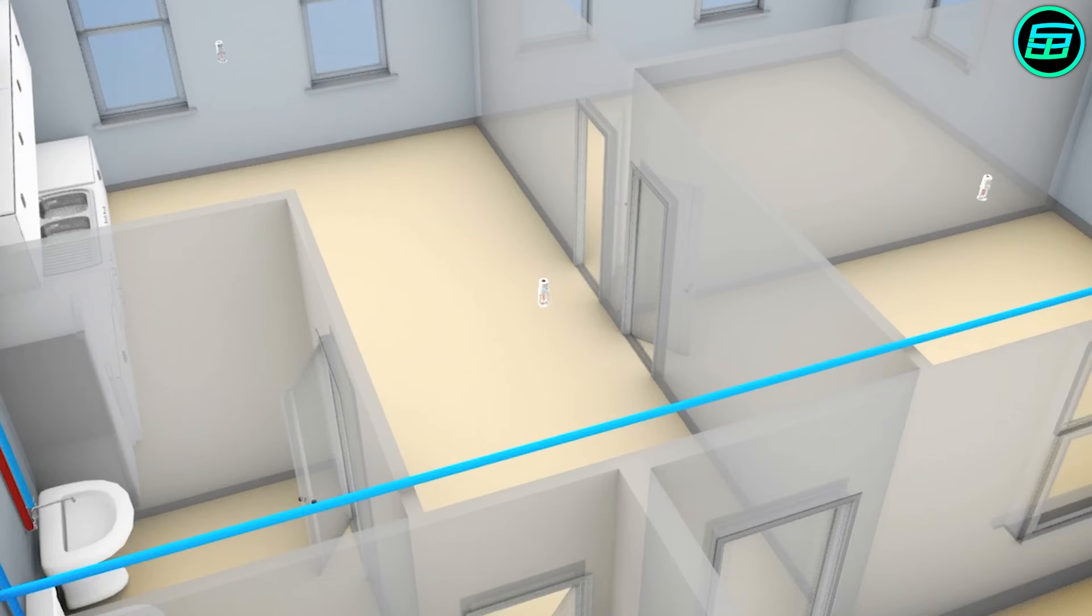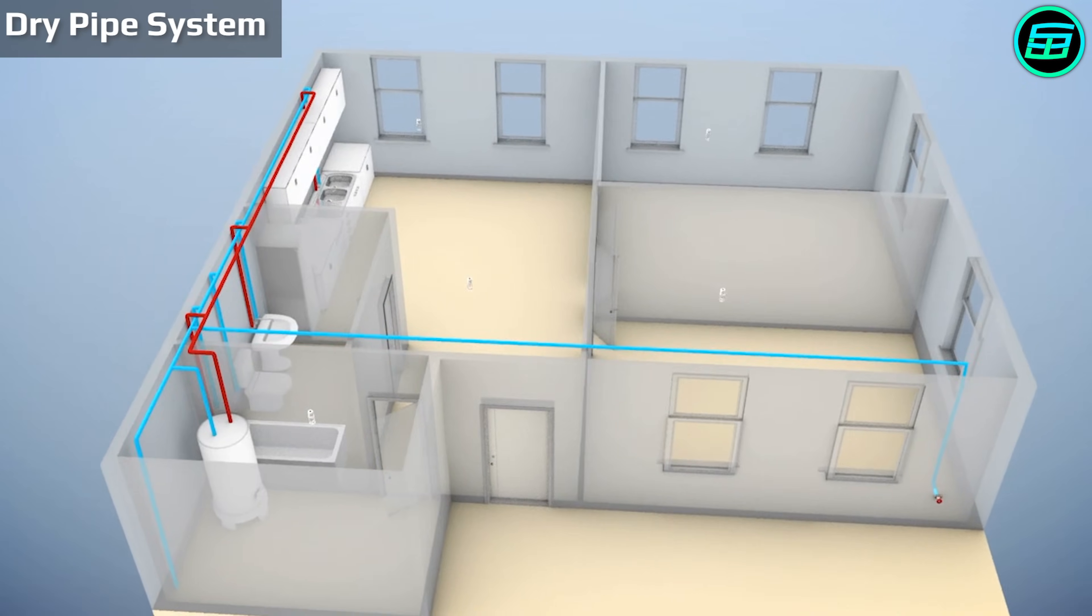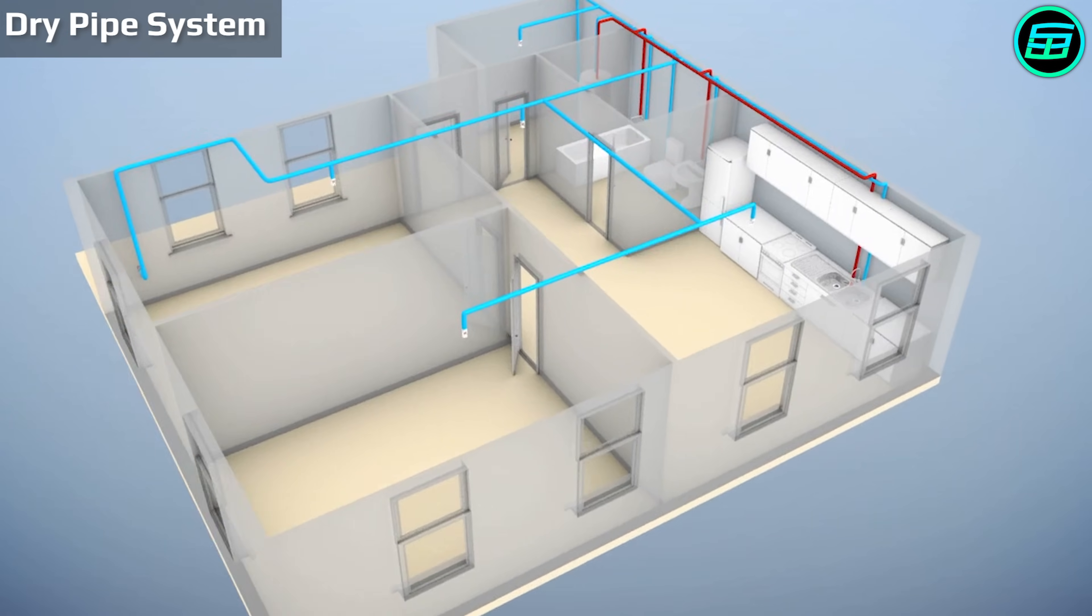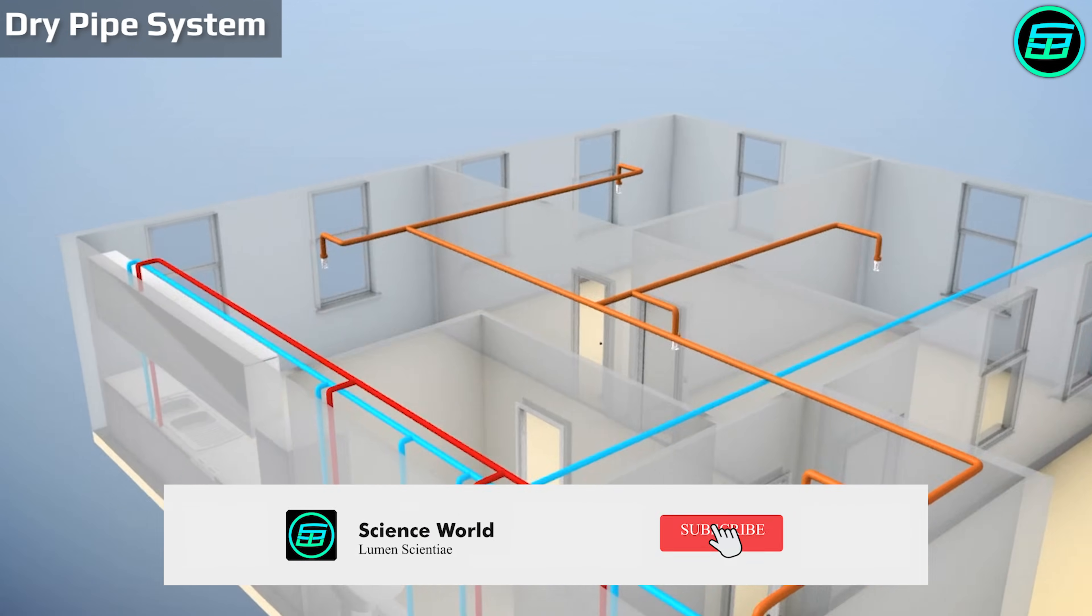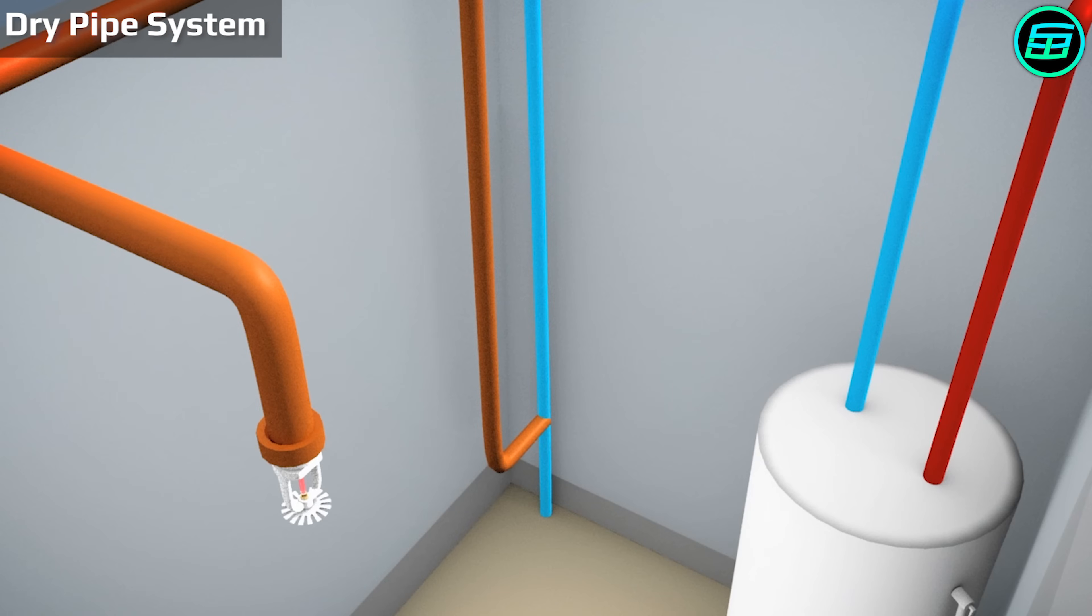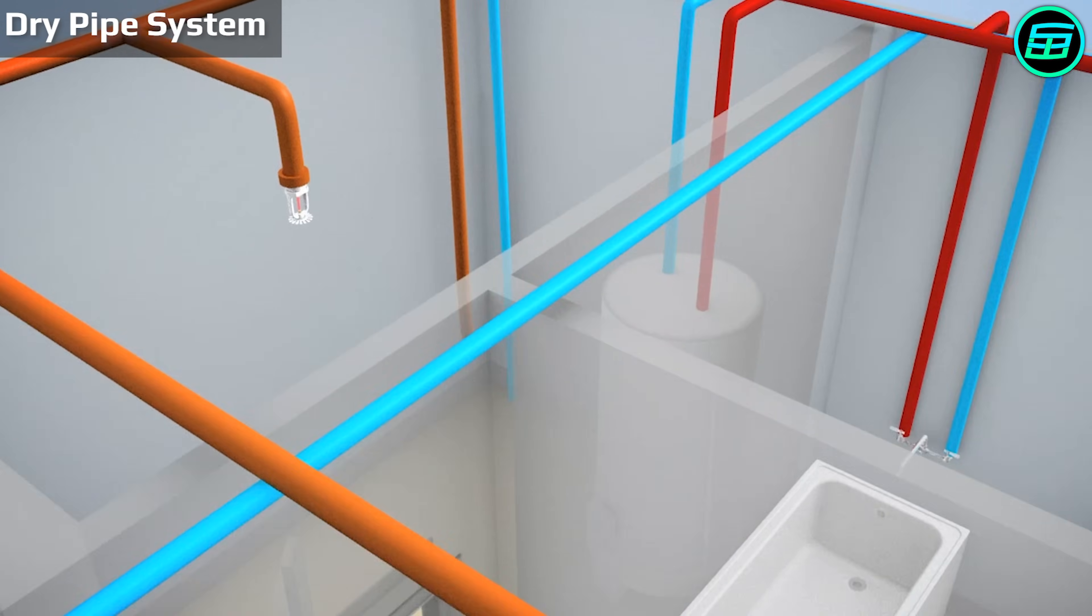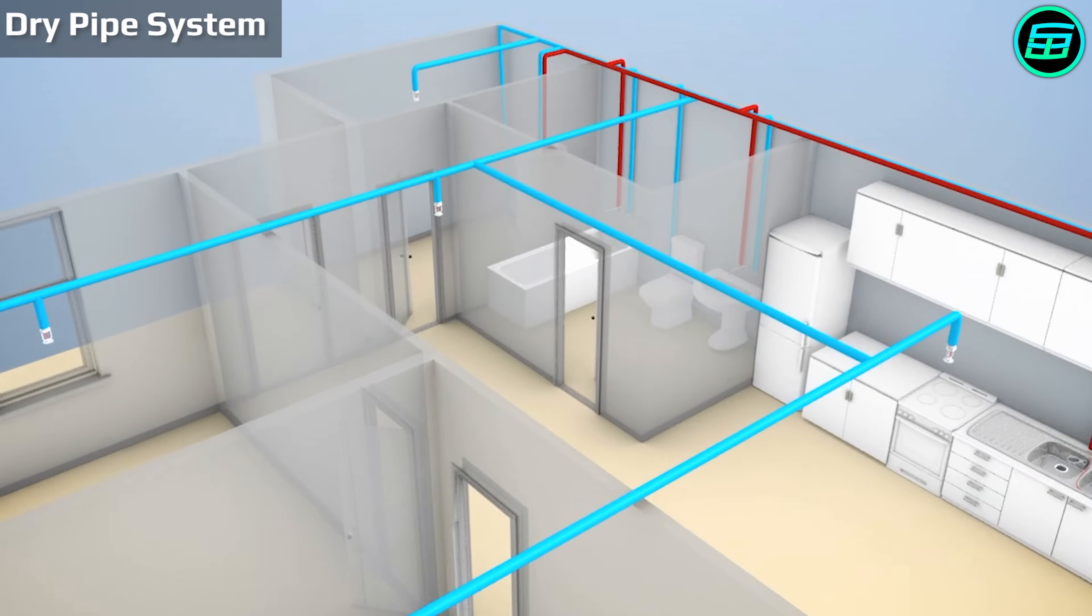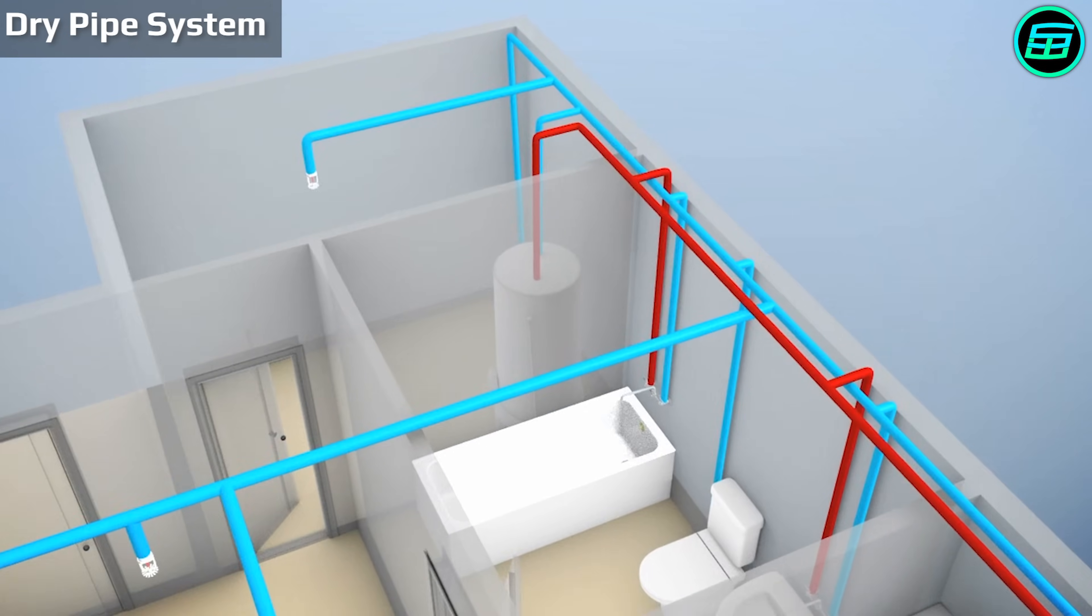Another type is the dry pipe system. In this, the pipes are filled with pressurized nitrogen which is released if a fire activates the valves in the sprinkler head. The pipes then fill with water, which is discharged over the smoke or flames. Dry pipe systems are widely used in cold climates since there's a high risk of frozen pipes preventing an emergency fire response.